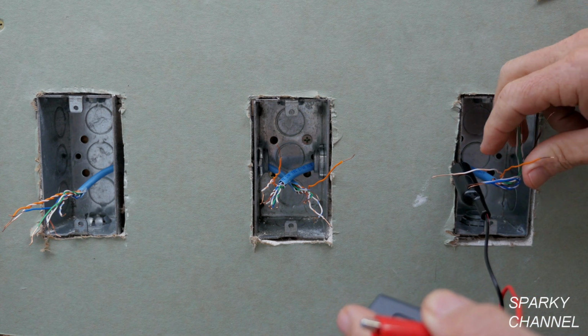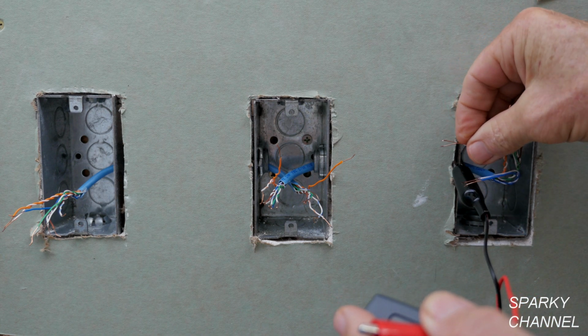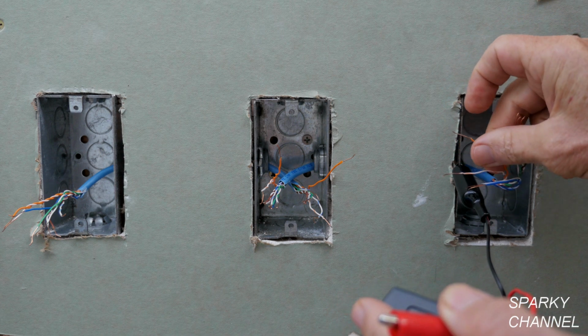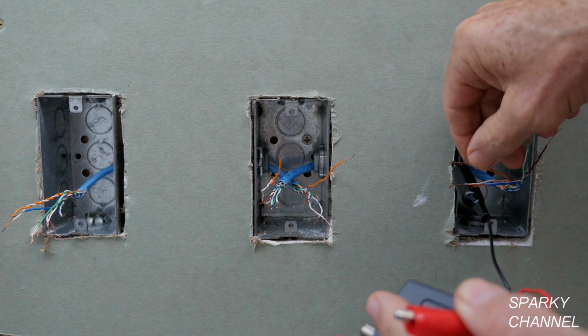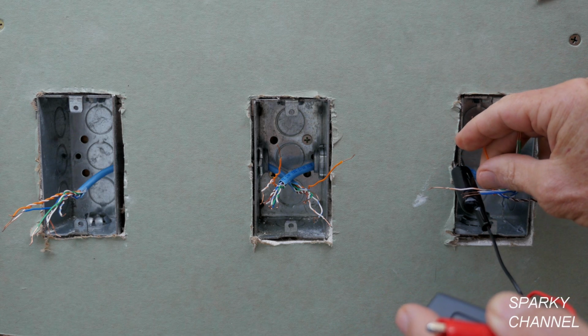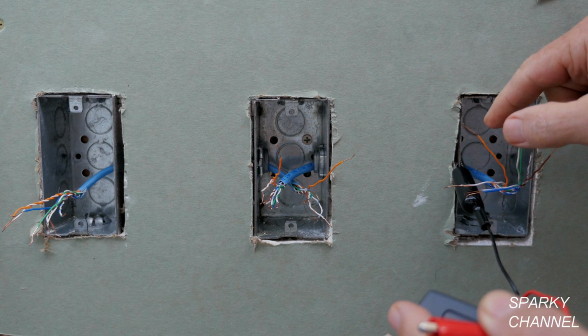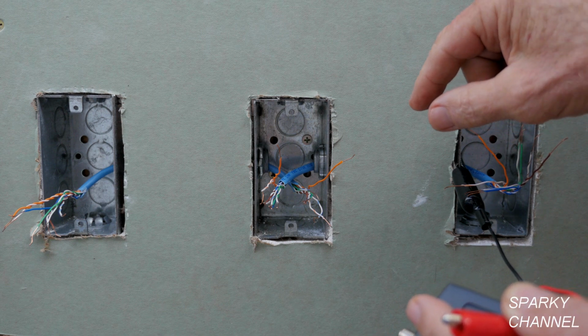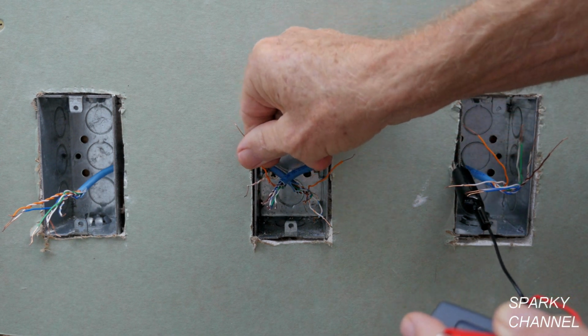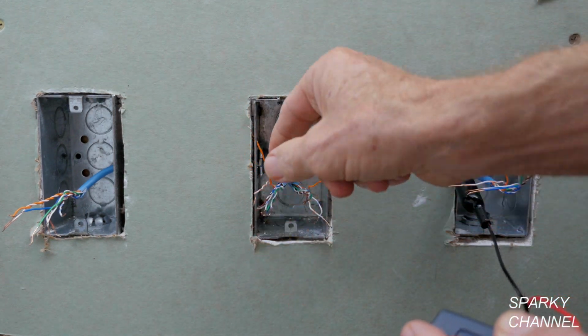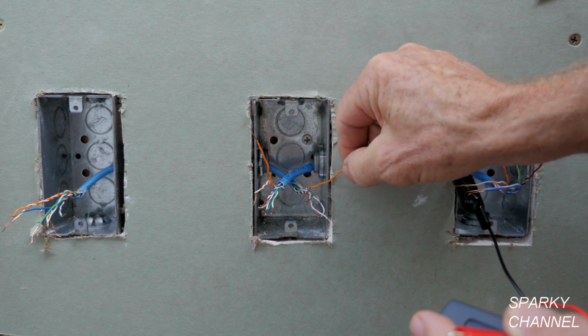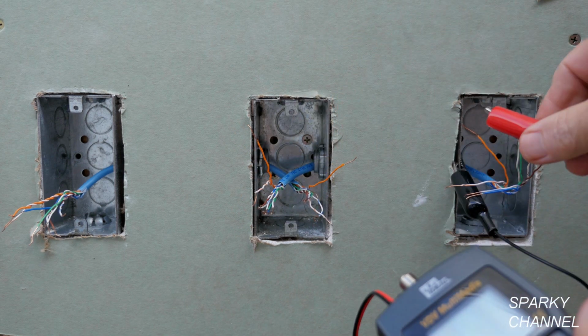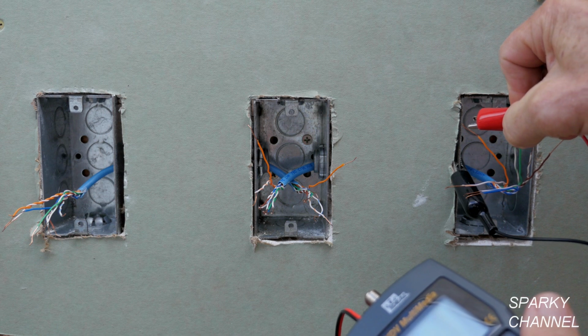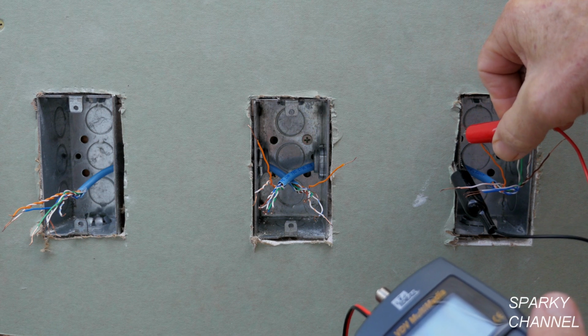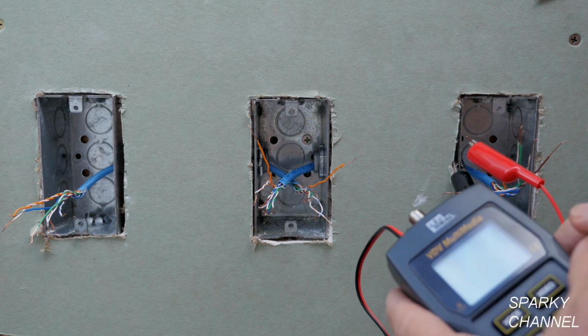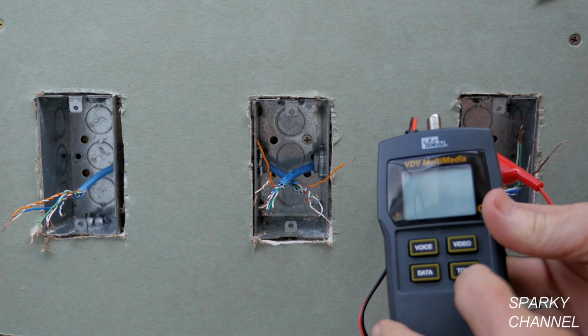When checking for continuity, you can look for a pair, a single wire, or the whole cable. I'm going to just do it with one wire. I'll select the orange wire and isolate that. Over here I have the orange wire of this cable isolated and the orange wire of this cable isolated. Now I'm going to put the red alligator clip on the orange wire right there, and turn this on to tone.